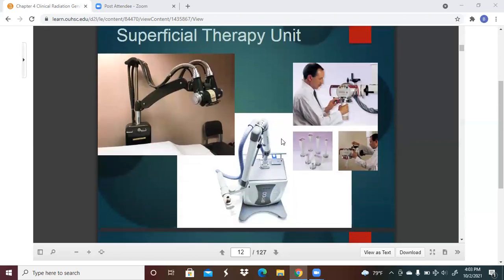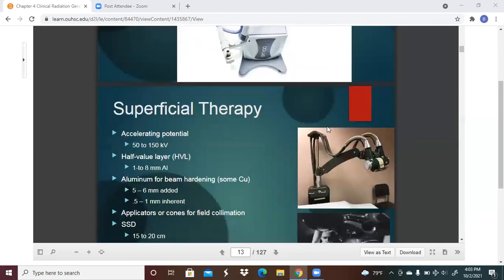So we've got a superficial therapy unit. We can see that we're a little bit higher than what we have been before, 50 to 150 kV. Half value layer, as you would probably expect, is increasing as well, from 1 to 8 millimeters of aluminum. The aluminum for beam hardening, with some copper included, is 5 to 6 millimeters added, or a half to a millimeter that is inherent. For applicators or cones for field collimation, as you can see there in the bottom right hand corner. SSD is about 15 to 20 cm, so not very far. Tube currents 3 to 8 milliamps, and it's useful for tumors confined to about 5 millimeters of depth.